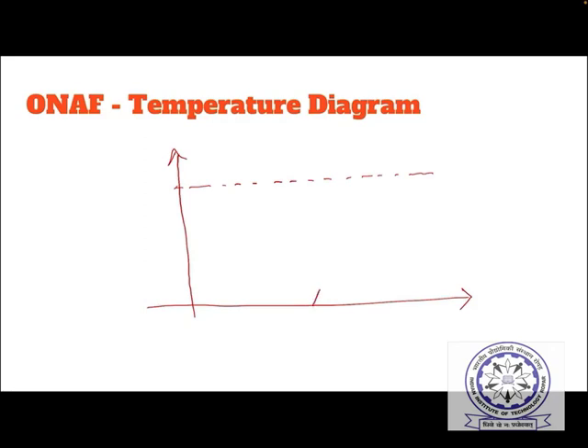So let me draw first the outer portion. This is 53 degrees centigrade and 73 degrees centigrade, point E. This is point D. And the hot spot temperature is around 75 degrees centigrade. Now there is more drop from copper to oil. This is around 20 degrees centigrade, say.